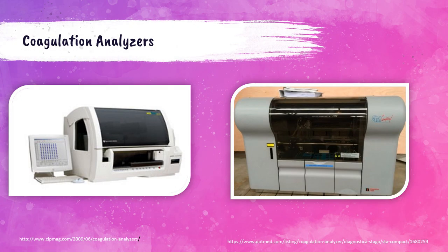There are two different kinds of coagulation analyzers. The ACL Top on the left and the STAGO on the right both perform tests like PT, PTT, D-dimer, fibrinogen, etc. The main difference is their methodology. The STAGO uses a mechanical clot method: the patient's plasma aliquot contains a tiny magnetic ball that rocks inside the tube, and when a clot forms the ball stops moving — the time recorded is the result. The ACL Top uses a photo-optical turbidimetric method. Both produce very reliable and accurate results and are easy to use.